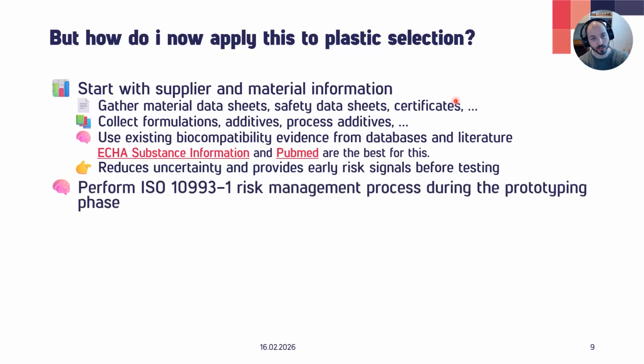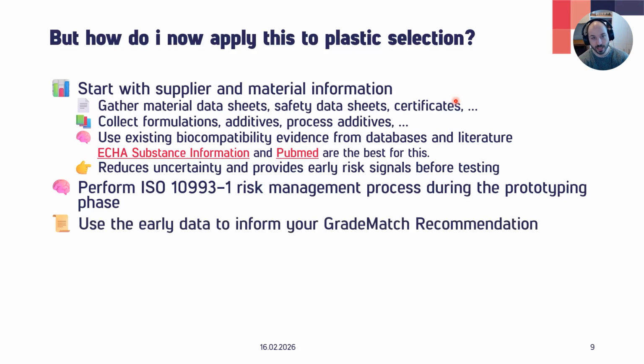Then on these substances, these potential red flags, you perform an ISO 10993-1 risk assessment during the prototyping phase. So very important, before you do the material recommendation, you run this. And that can in turn inform your GradeMatch recommendation, so your recommendation of your plastic selection, basically. So you have the candidates, and then you have the recommendation. If you're not very aware of how plastic selection works, I think I have a video on it. Check that one out. And your biocompatibility risk assessment can then inform your recommendation. So that is what you will move on with during the development phase.